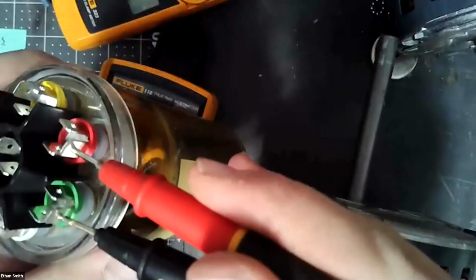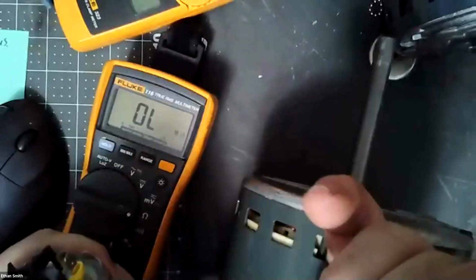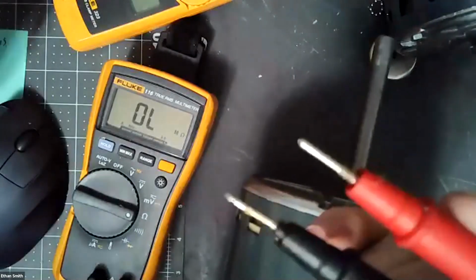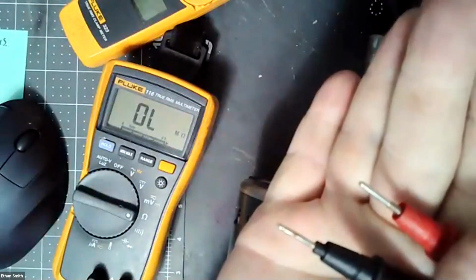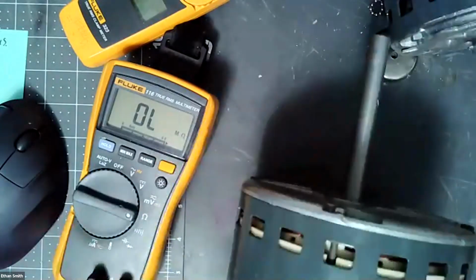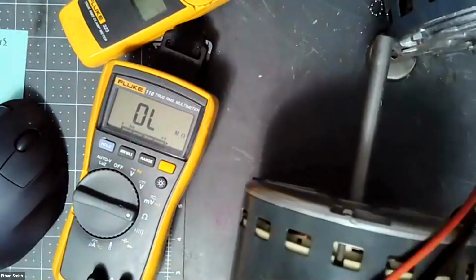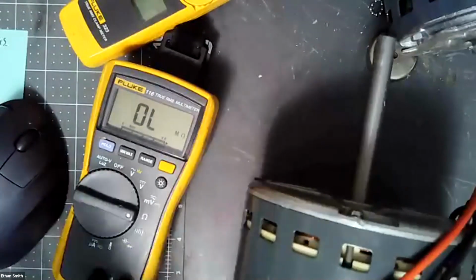You guys have kind of struggled, watching me struggle to keep my leads on stuff. It's because my tips are chewed to pieces. Okay, they like to slip around and slip off because I don't actually have a tip on that one anymore, and that one's bent and arced on. So if your leads are in bad shape, something that will help you get good electrical readings is simply replace your leads, guys. Get good quality leads. Hardened tips go a long way. But yeah, loose connections will give you those fluctuating voltages up and down.